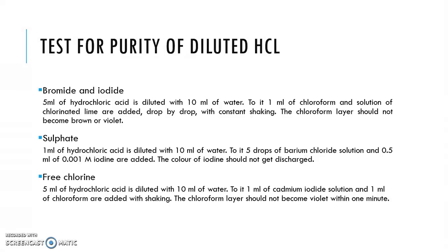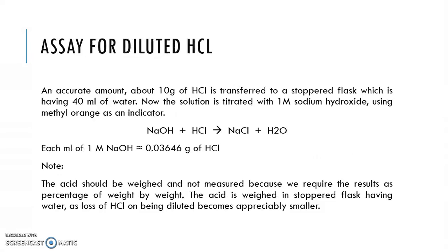For checking sulfate: when hydrochloric acid is added to water and barium chloride, the solution should not discharge the iodine color when iodine solution is added. If it discharges the iodine color, sulfate is present. To test for free chlorine, the chloroform layer should not become violet when hydrochloric acid is added to water with cadmium iodide and chloroform. If it becomes violet, free chlorine is present.